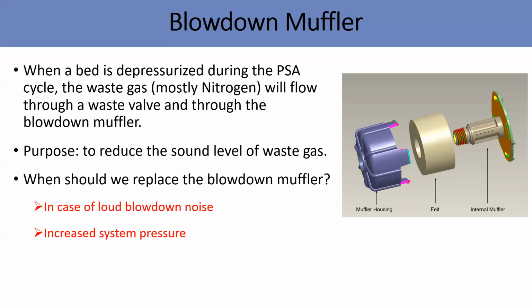So normally the common problem is you get loud noise and an increase of pressure on the system. So you can check this particular blowdown muffler. It happens because the lifespan of this blowdown muffler can be 2 years. Sometimes, due to too much moisture in the area, it breaks up very fast, and eventually you get pressure increase and noise.